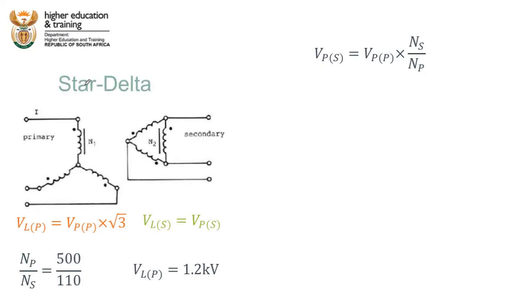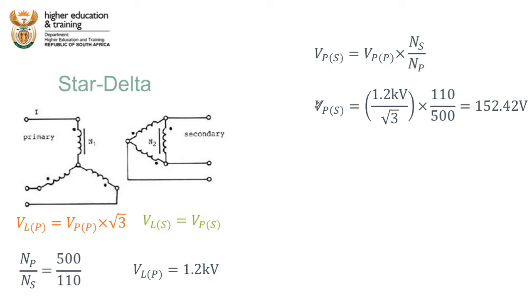For star-delta: the primary is star, so we divide the line voltage by √3 to get the primary phase voltage, then multiply by the turns ratio 110/500, giving 152.42 volts for the secondary phase voltage. Because the secondary is delta, the line voltage on the secondary equals the phase voltage — so the secondary line voltage is 152.42 volts, which is a different and lower answer than before.